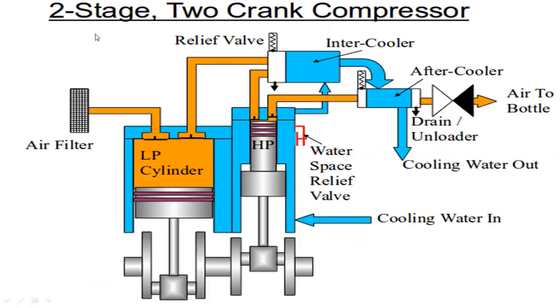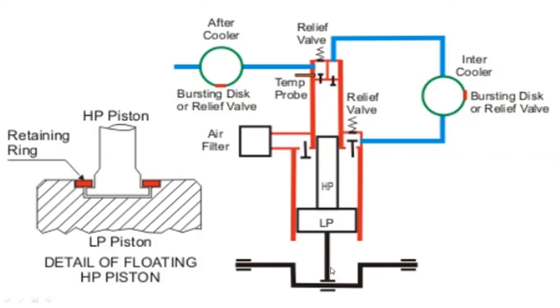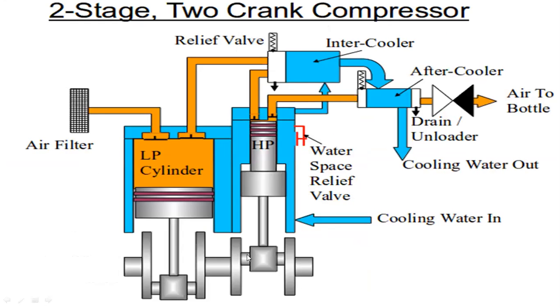So far we have seen a two-stage single-crank arrangement where both the low-pressure and high-pressure pistons are connected to a single crank. Now if we look at a two-crank arrangement, we have two cranks continuously rotating. Through the air filter, air enters the low-pressure cylinder; as the piston pushes up, pressure goes into the next stage, gets cooled, comes back to the high-pressure cylinder, and the piston again pushes it. Then it goes to the aftercooler with cooling water drain, and finally to the air bottle or reservoir. Temperature increases as air is compressed and its volume reduces.